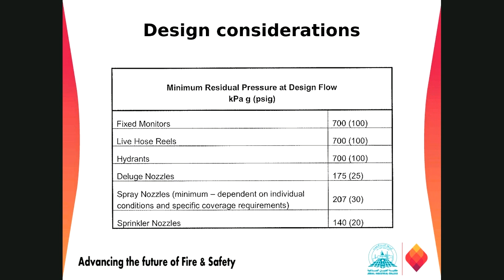And now the pipe velocity. The maximum velocity in the firefighting piping, as per NFPA 20, is 6.1 meters per second. Now when I talk about NFPA 20, I am only talking about this: our fire pumps, this is our discharge line and this is our suction line. So only 10x diameter, right? 10 times the diameter this side and 10 times the diameter this side.